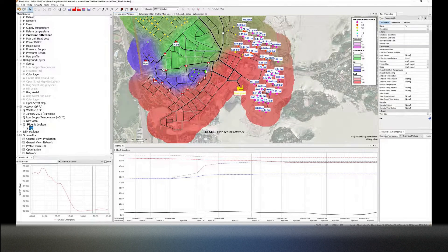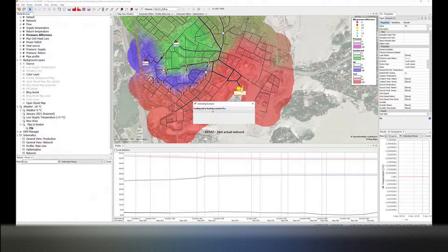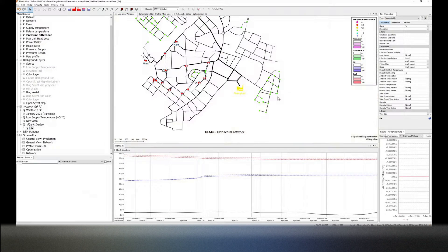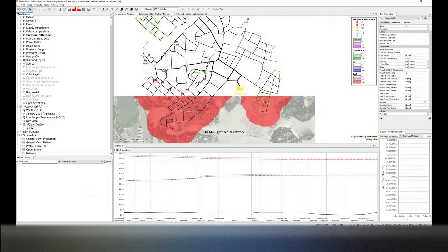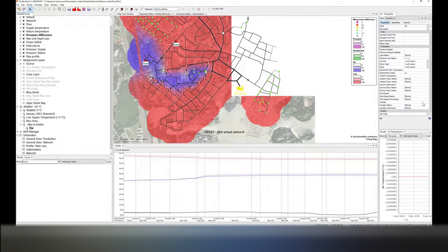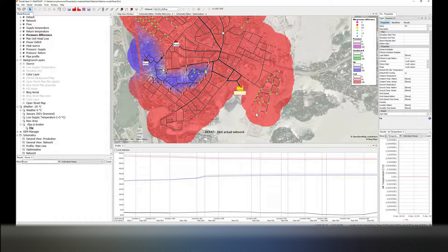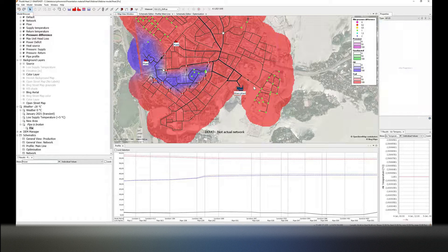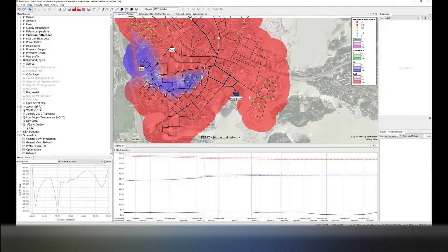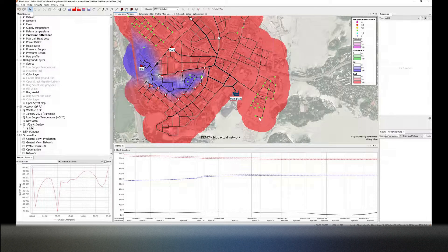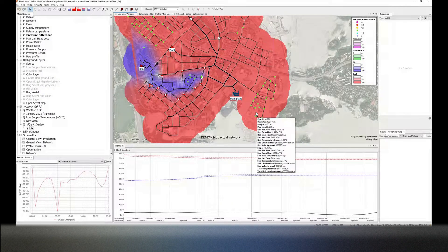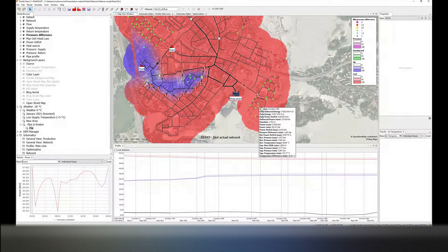So what the fix would just be is that for our main plant we would have one extra control point be in this island here, and thus it would be pumping extra head and then creating enough flow for those points there.